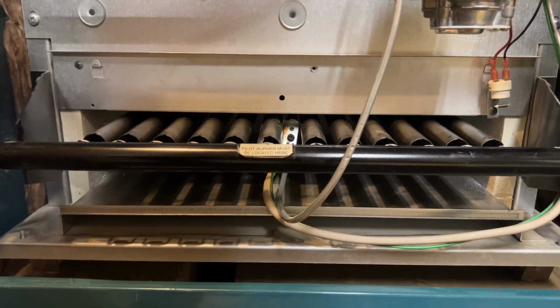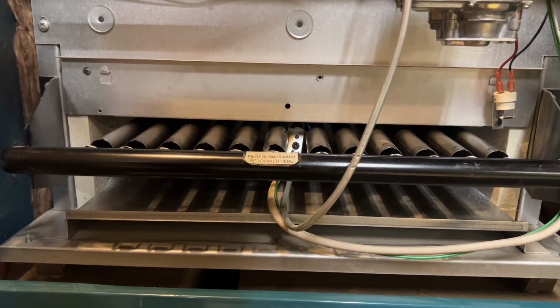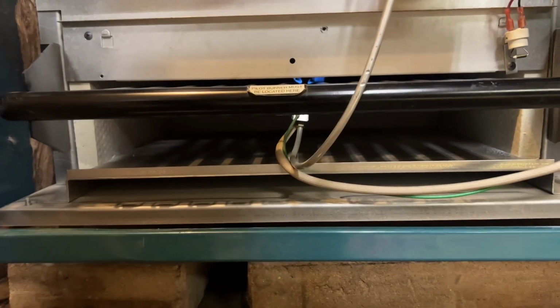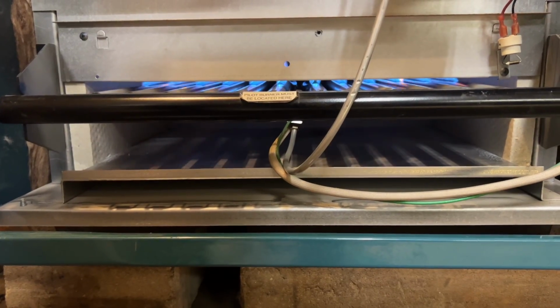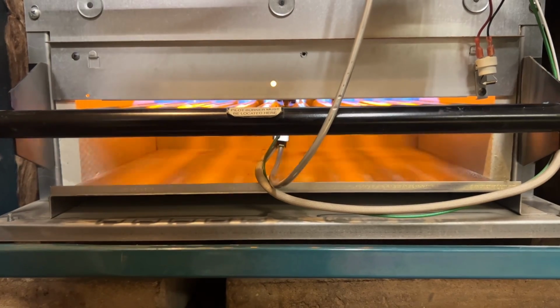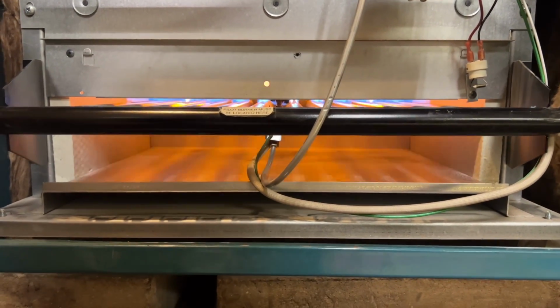Stay tuned. There's that thermostat relay. And what just kicked on is our fan in a can. We'll talk about that next. Main valve opening, slowly opening since it's a step valve. Nice, good, solid blue flames. Very pleased. And here comes main ignition. Houston, we have ignition.